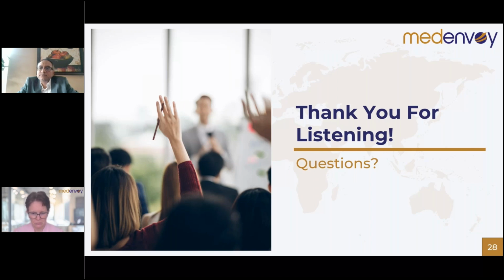Got it. Thank you. Okay, we'll do one final question. How can we implement Article 10a, informing authorities about potential product discontinuations, into our PMS system and PMS relevant SOPs or QMS? Any significant changes must be reported to your notified body to begin with. So the change control and your embedded mechanisms for notifying significant changes to your notified body, that is your first port of call. And then, of course, depending on the nature of the change, there can be other mechanisms, but that is the first port of call.